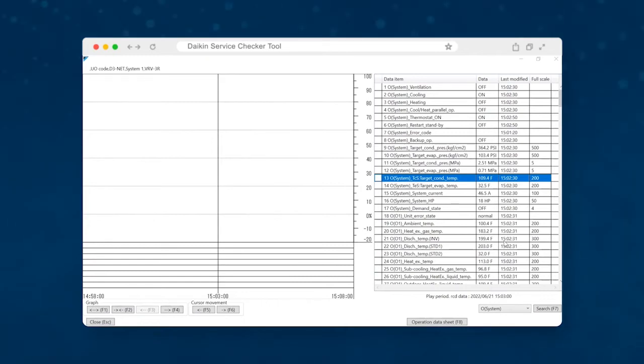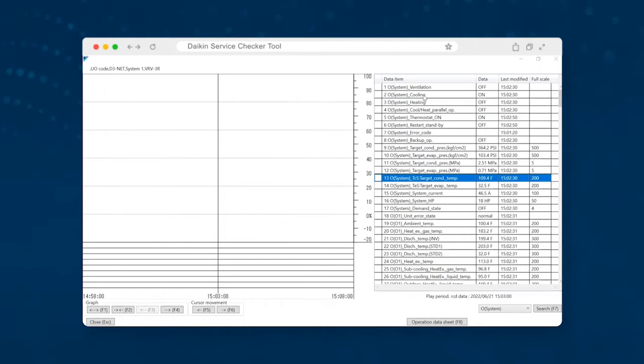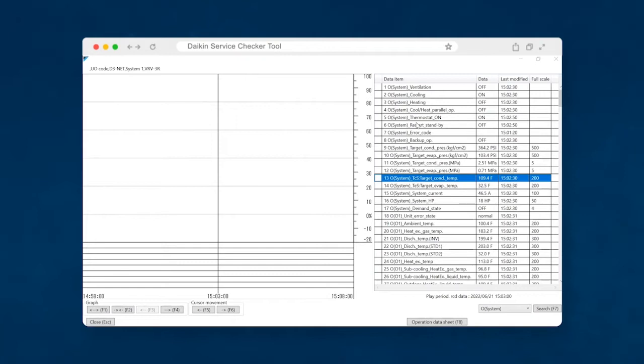The first thing that you will want to look at is what mode is the unit operating in? And so if you come up here on the service checker tool. So this is the service checker. This is the data operation displayed on the screen. So this is actually data that we have previously recorded from a job site. But if you were looking at the data live, this is exactly how it would look.